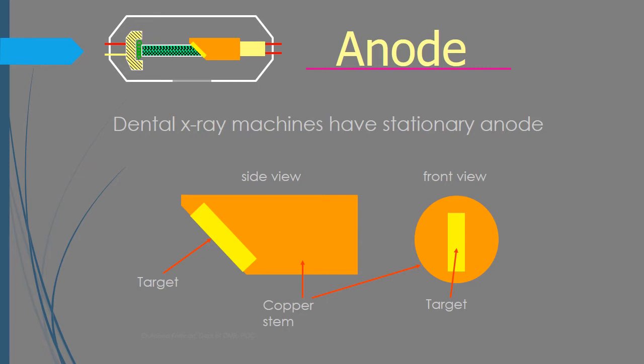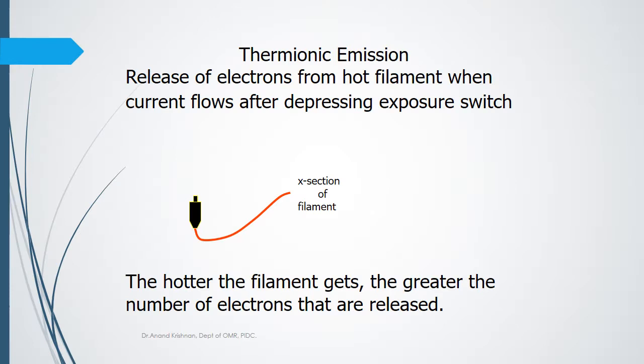The problem with the stationary anode is excessive heat generation. Even with the copper stem dissipating heat, wear and tear of the tungsten leads to pitting, affecting the quality of x-rays produced. The stationary anode is used in intraoral machines because the power levels are low enough to avoid significant damage. For higher-powered machines, a rotating anode is used.